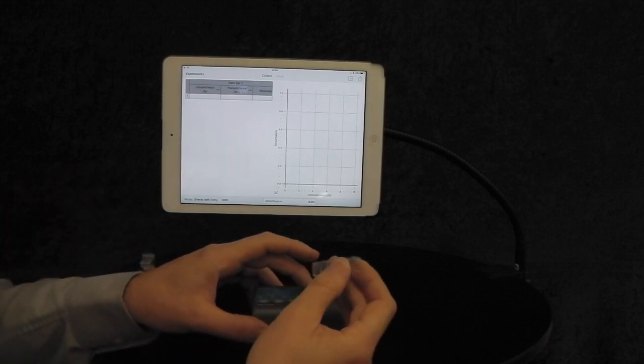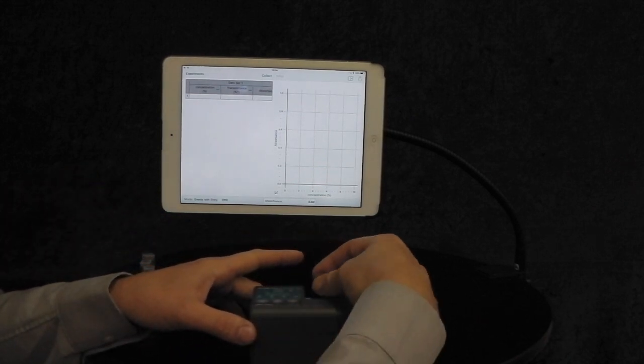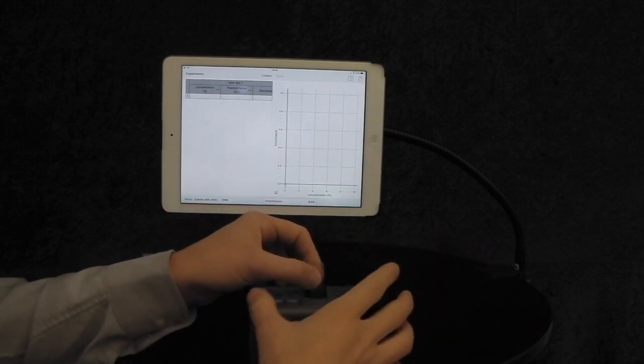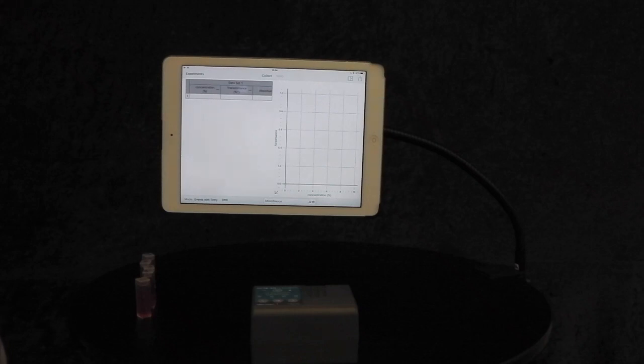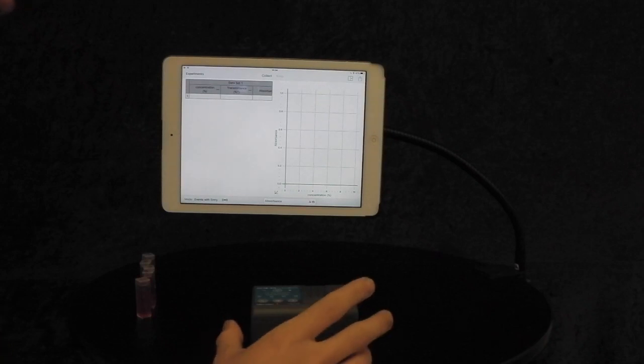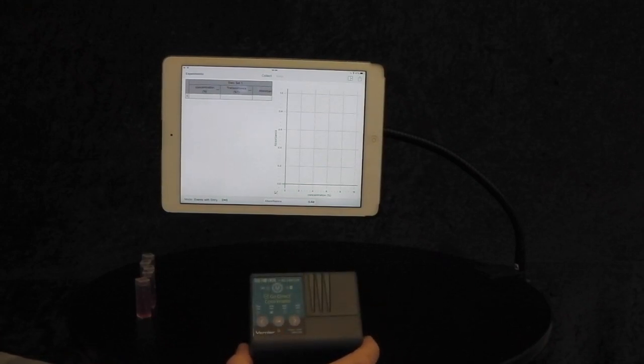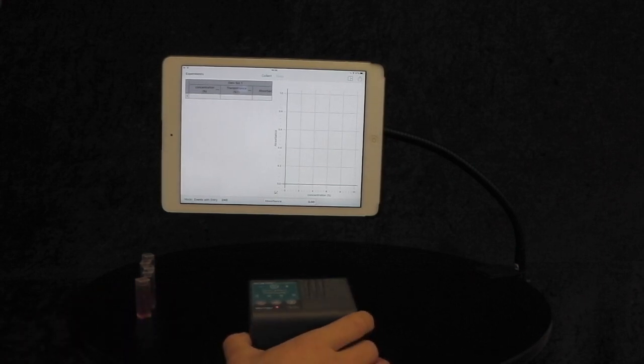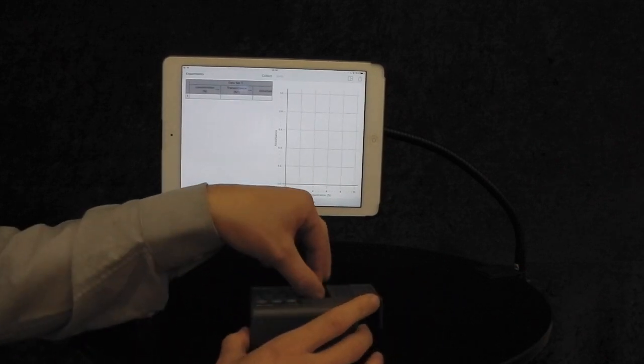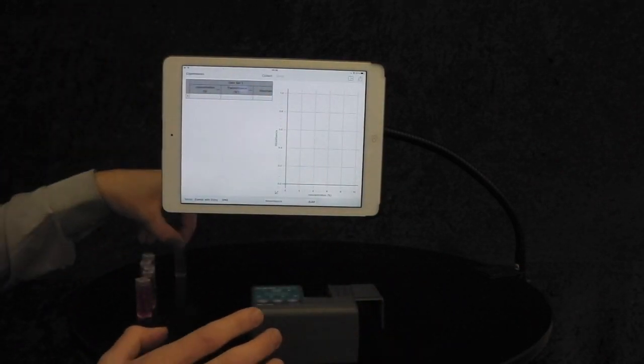First of all, insert a blank cuvette with the ribbed markers going that way. Press Calibrate. Red light will flash while it's calibrating. When the calibration is finished, it will stop flashing. I'll take the cuvette out, holding it by the ribbed sides again.